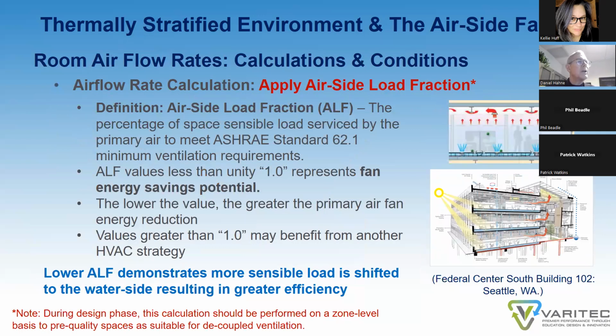So how do we calculate the air side, and how do we determine whether or not passive radiant 100% outside air systems make sense? Well, what we need to do in designing the air side is make sure that we define how much air is required for a room and for a building to comply with ASHRAE Standard 62.1's minimum ventilation requirements. And then you apply an air side load fraction rate.